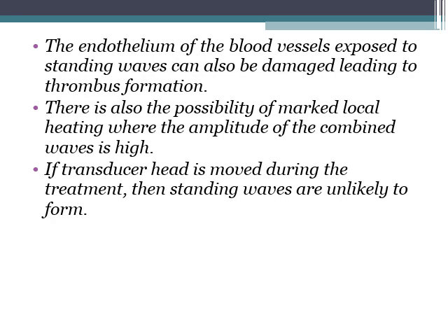The endothelium of the blood vessels, when exposed to standing waves, can also be damaged and form a thrombus. And there is also the possibility of marked local heating where the amplitude of the combined wave is high. So if we continuously move the transducer head or treatment head, there is less chance of formation of standing waves. So to avoid standing waves, we should continuously move the treatment head.